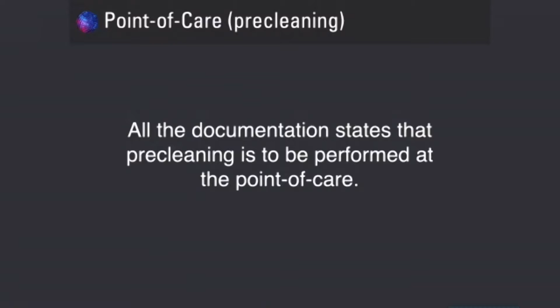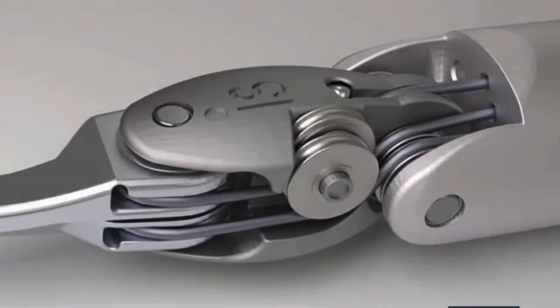Point of use or point of care pre-cleaning. So with the da Vinci robotics, it's a very big deal with pre-cleaning, keeping your instruments moist, right? Can you look at all of this on a distal end of an SSI instrument? All of the areas that can trap all this really nasty bioburden, and the ability to try to brush all this is quite difficult. And you have to take your device and actually articulate the arm in different positions to be able to get in there and clean it.